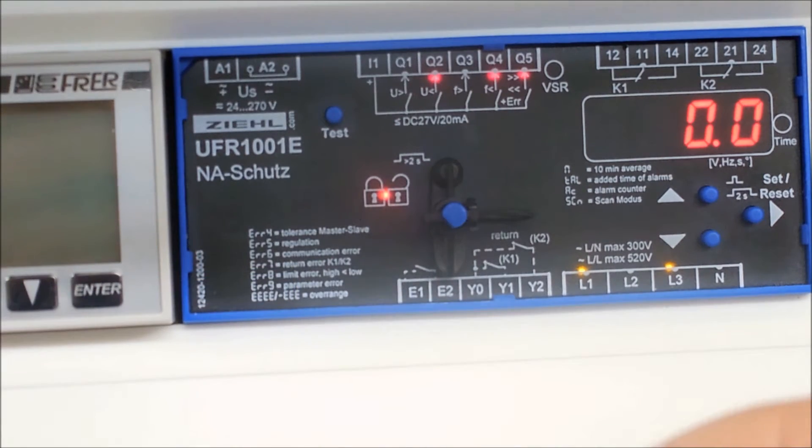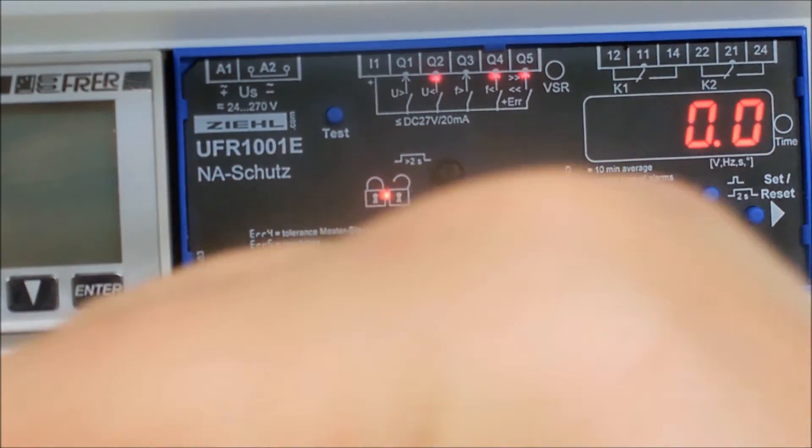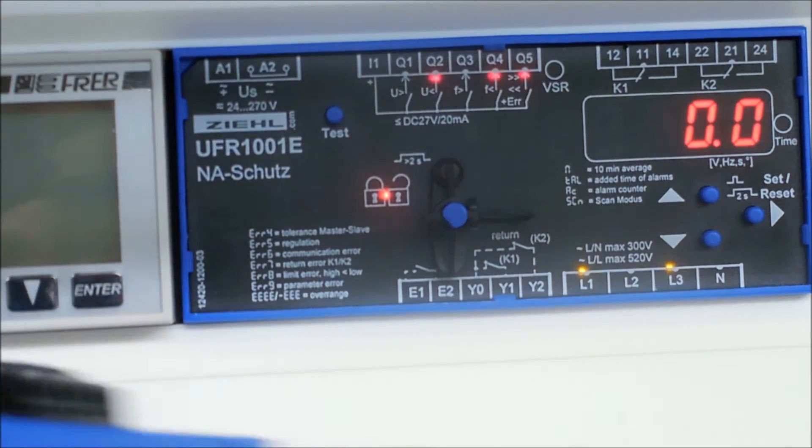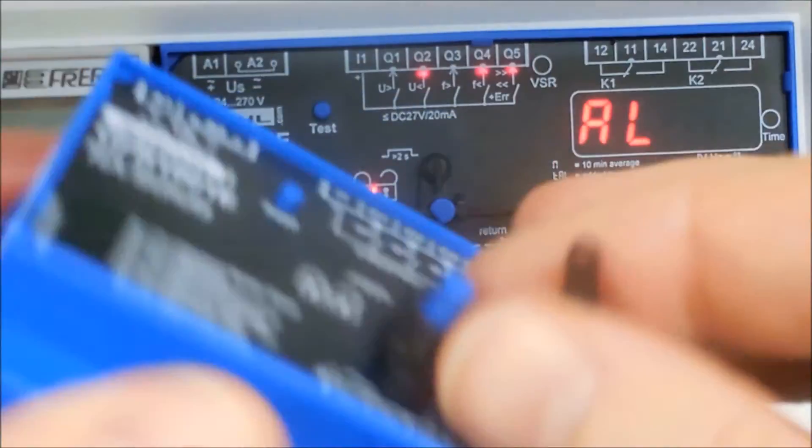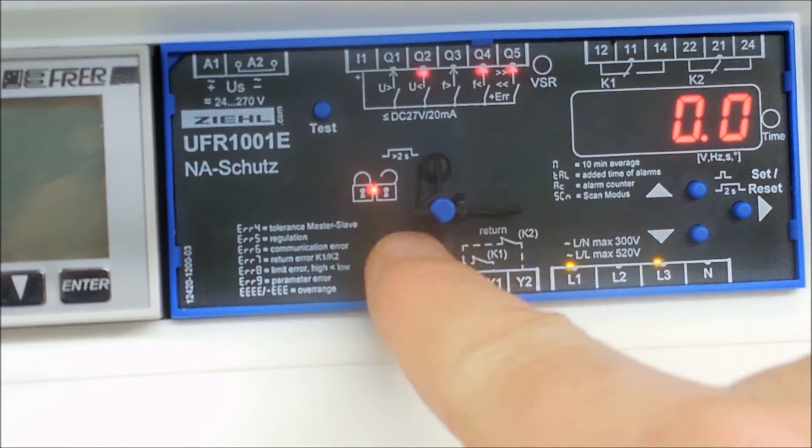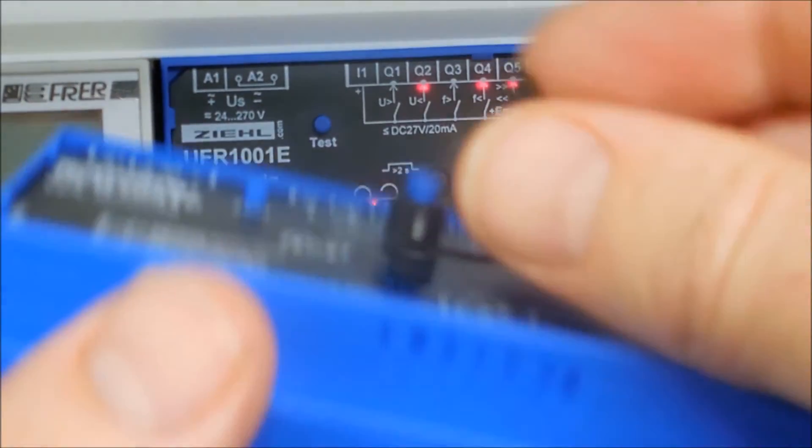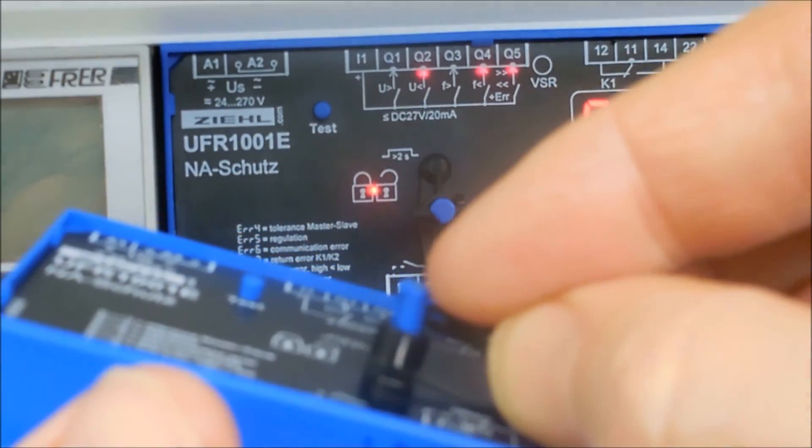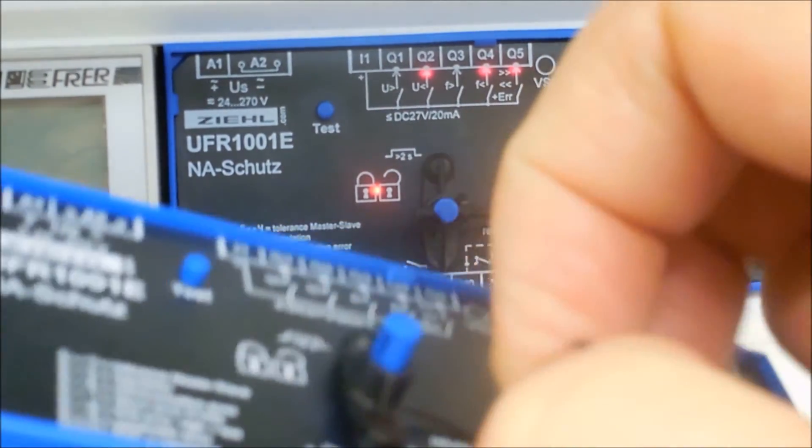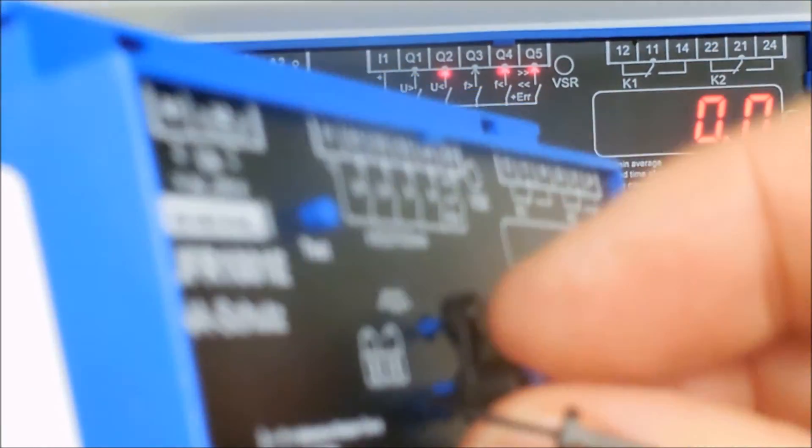We're now going to switch it from the supervision mode to the lock mode and we're going to do this by rotating this piece of plastic here that's to the right of the LED. It comes with this wire seal, plastic seal sorry, from the factory. So you just take that out and you take it around and rotate it around and you will see that there is a pin there. That is the pin you have to press down on.